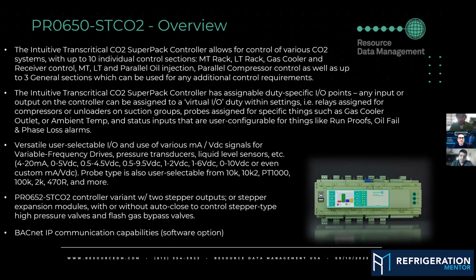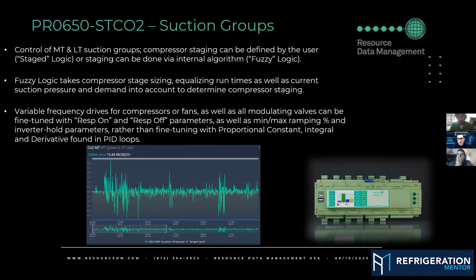For OEMs, this is great if you need to connect to a third party front end or something. The controllers do BACnet IP as a software option, so you have that available if you need to. I know BACnet is becoming more and more involved in refrigeration, like it is with HVAC. BACnet's huge in the HVAC industry, and we're finally starting to see it in the refrigeration industry. Yeah, I definitely prefer BACnet to Modbus. BACnet has that self-actualizing quality where it just sends things, and it should work ideally. Sometimes companies don't exactly follow the standard, but with Modbus you have to write your own templates. You can do that in the data manager if you need to, but it's tedious to go through all your registers and write all that out.